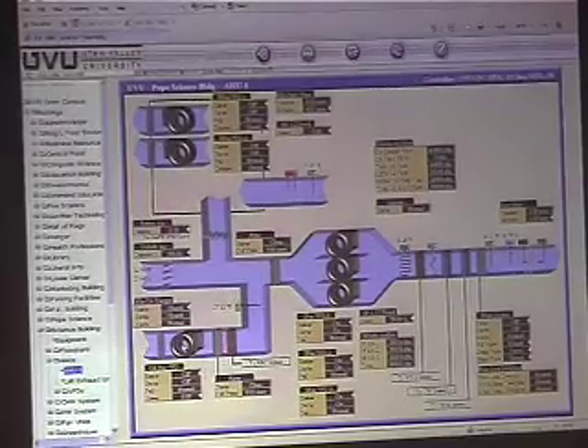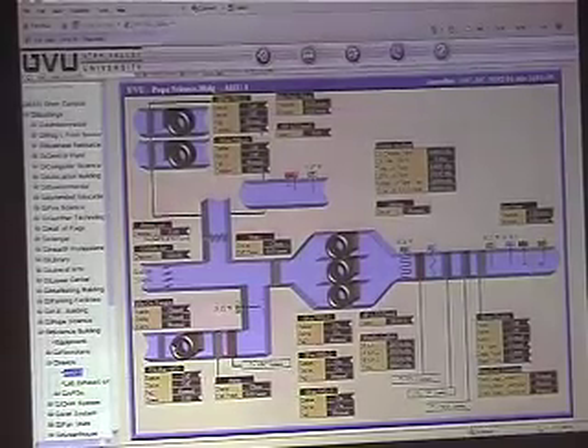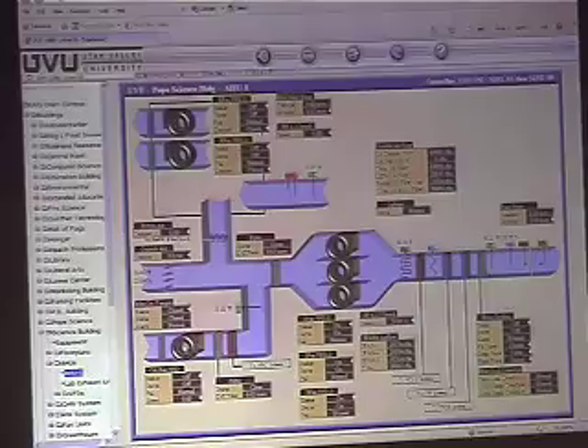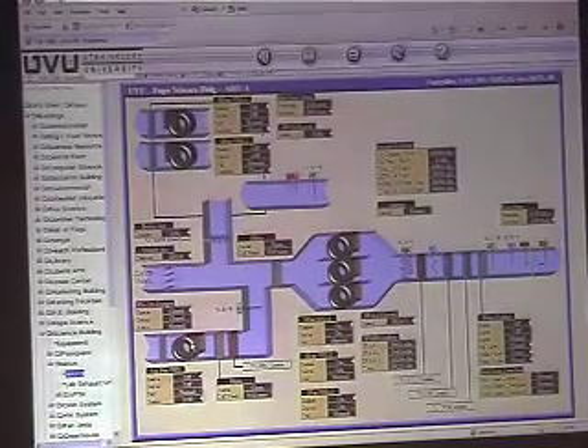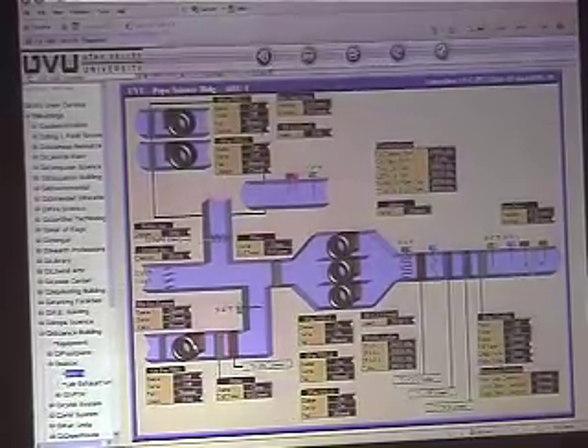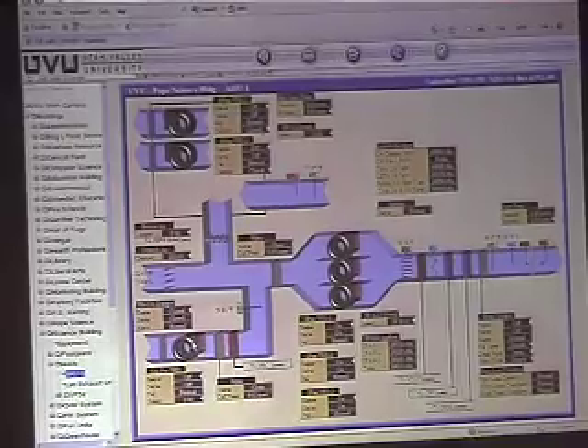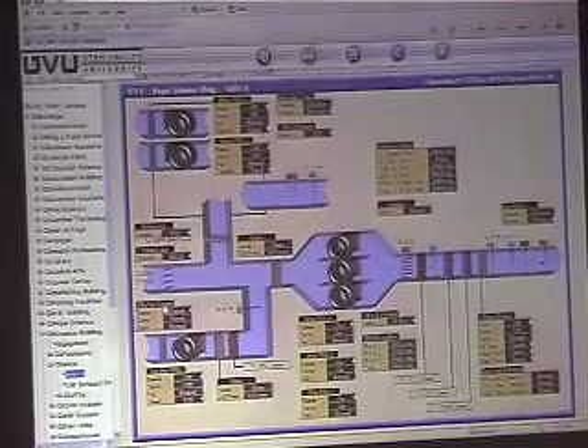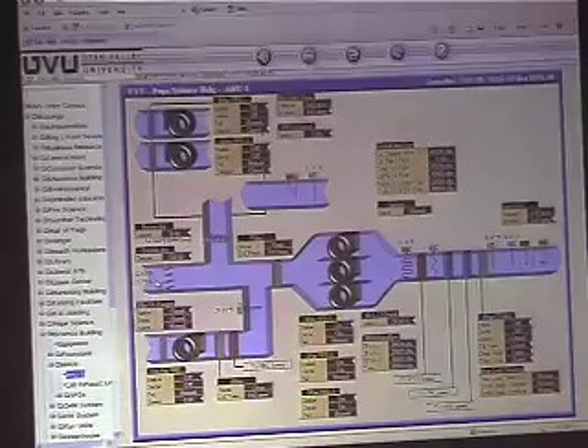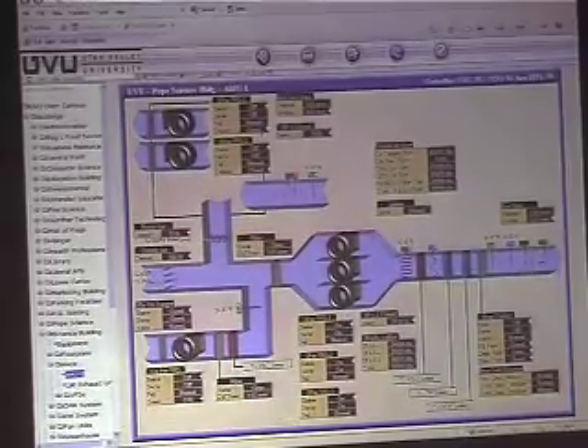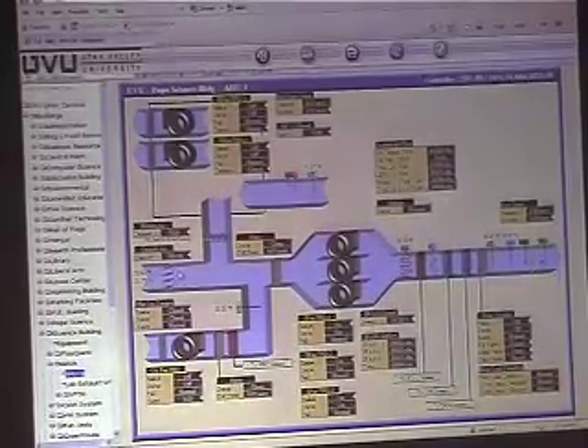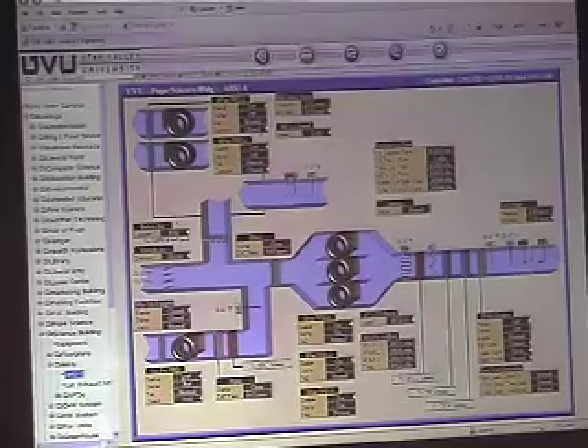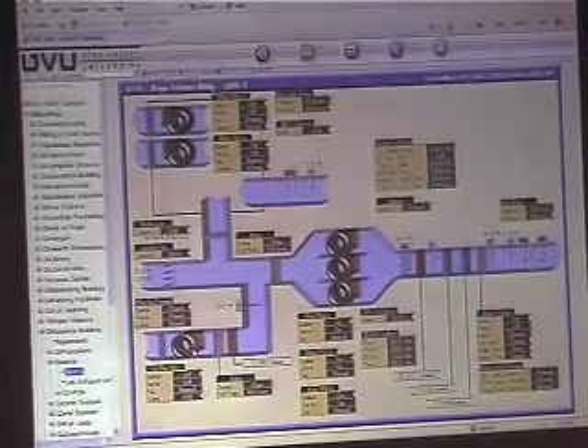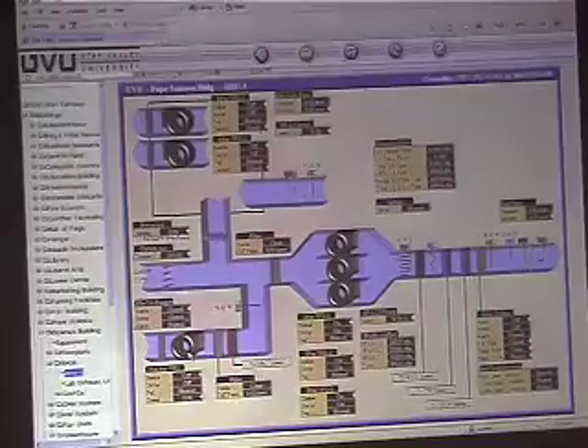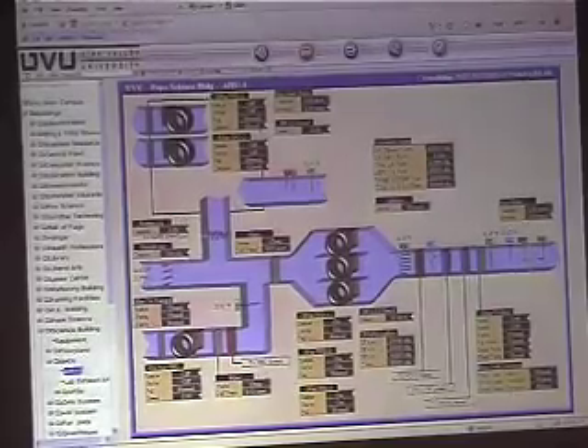Then it'll switch over to the outside air fan on this side here. This fan operates if it's below 44 degrees outside. Otherwise, it just stays off. So most of the time, especially in the spring and summer and fall, you'll be bringing in outside air through here. This fan here does the same thing. It modulates its speed to satisfy the airflow that's being exhausted.